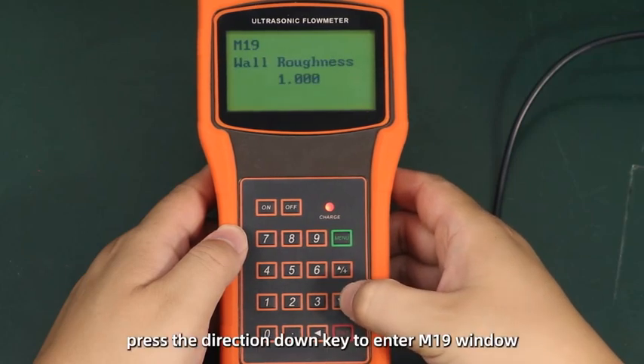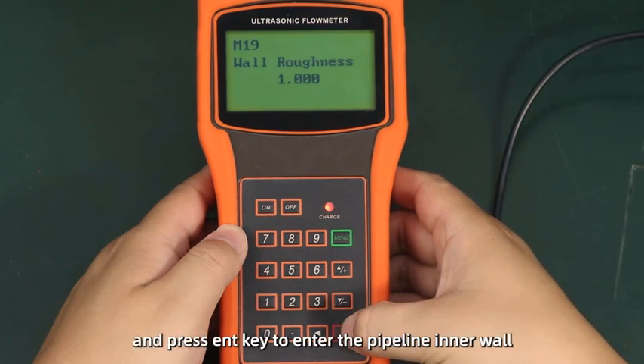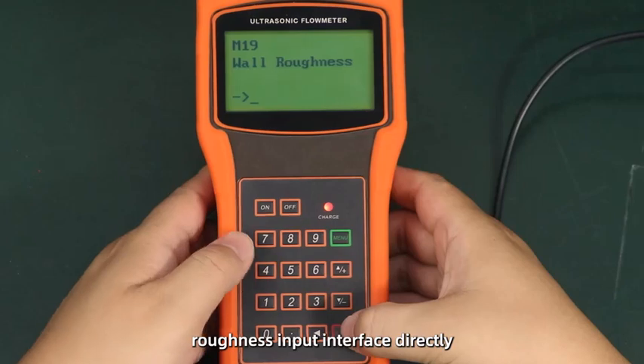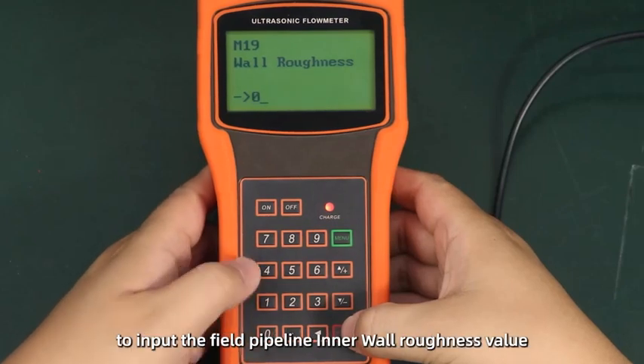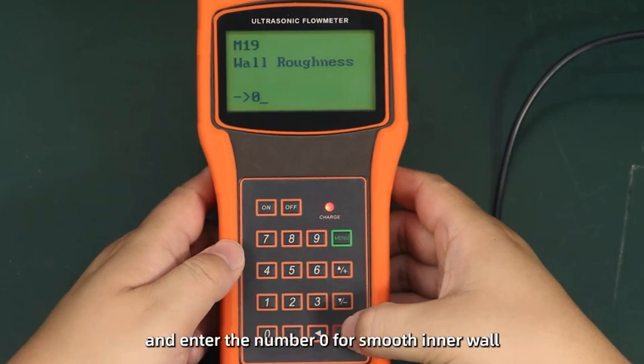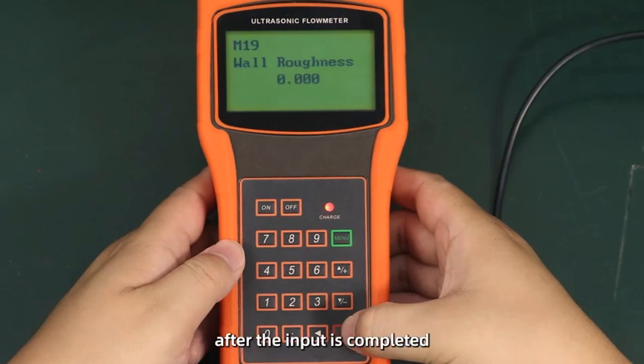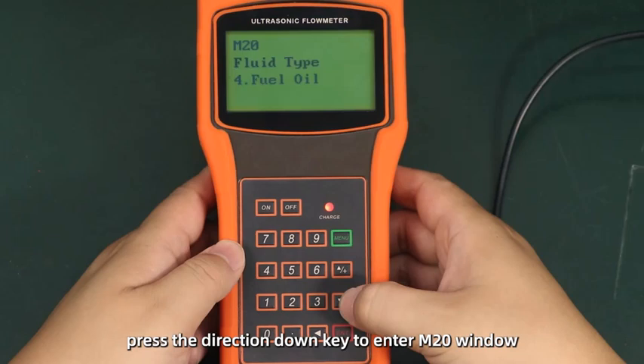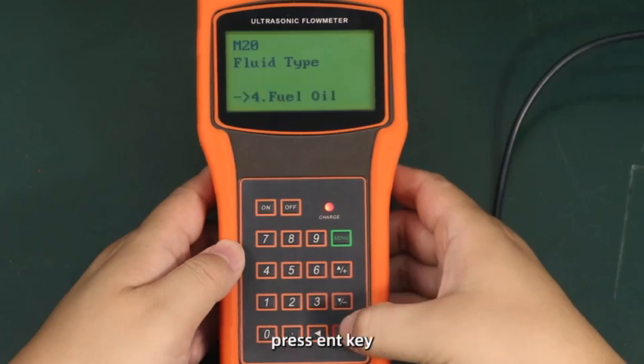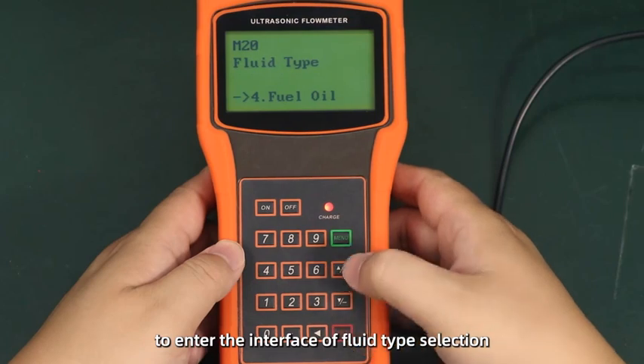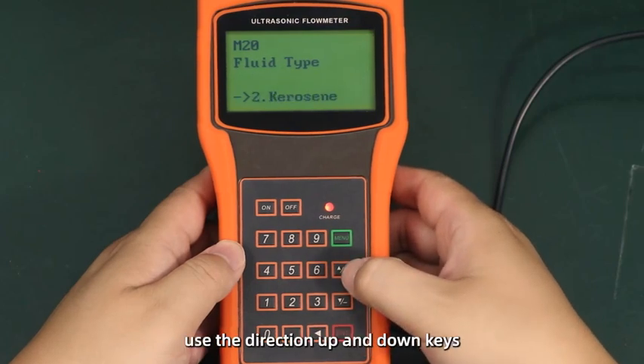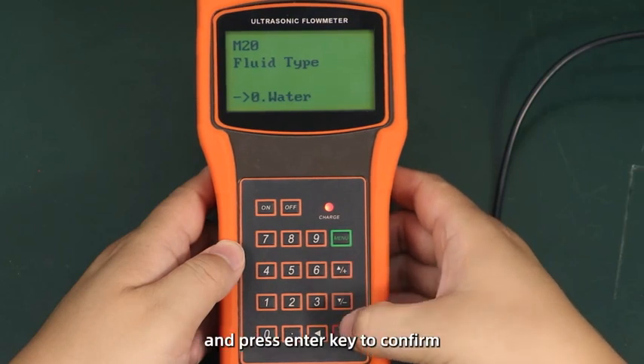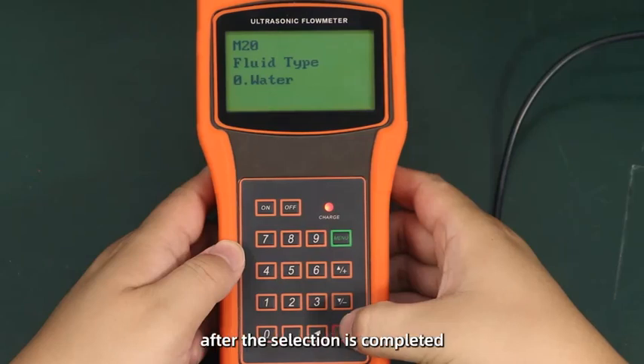Press the direction down key to enter M19 window, and press ENT key to enter the pipeline inner wall roughness input interface. Directly use the numeric keyboard to input the field pipeline inner wall roughness value, and enter the number 0 for smooth inner wall, and then press ENT key to confirm after the input is completed. Press the direction down key to enter M20 window. Press ENT key to enter the interface of fluid type selection. Use the direction up and down keys to select the option that matches the type of the medium to be measured on site, and press ENT key to confirm after the selection is completed.